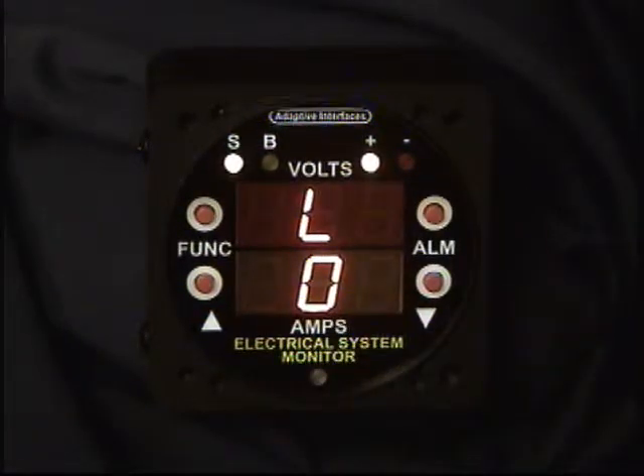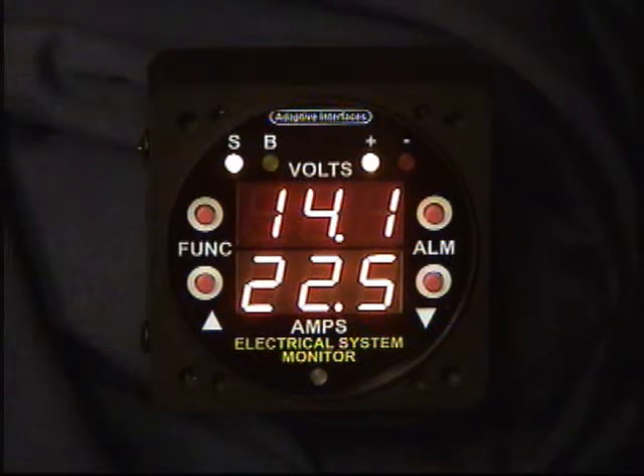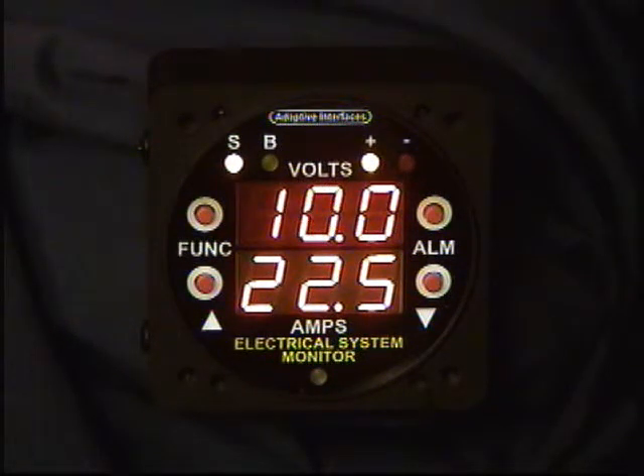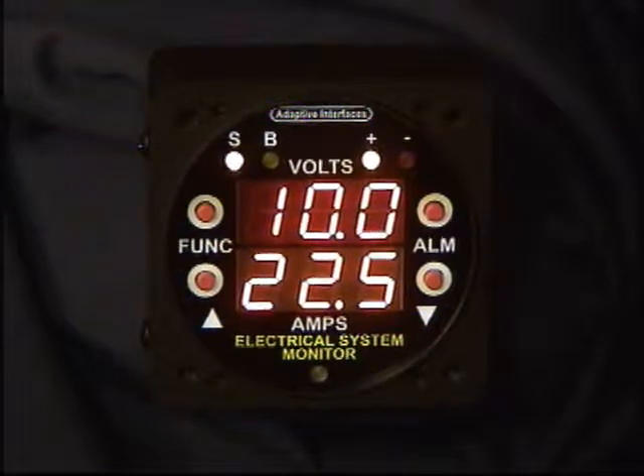Let's go ahead and go back to the main operating mode of the instrument. And what we'll do for the last thing is demonstrate an alarm condition for the instrument. In this case, I can control the voltage going to the instrument between a battery voltage of 14 volts and 10 volts. 10 volts will put the instrument into an alarm condition, and we'll see what happens when that starts. We're now at 10 volts. Unfortunately, there is a timer in the instrument, so the instrument has to wait 2 minutes before it goes into an alarm condition. So we'll stop the tape and show what happens after 2 minutes, and we'll get back to the demonstration.